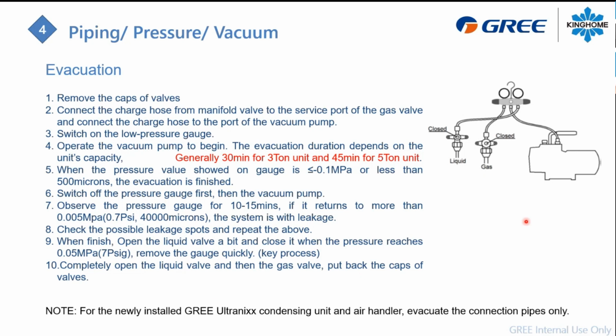So you will attach your vacuum pump, and then you will need to make two different vacuums, one for the liquid line and the other one for the vapor line, because the coil is already holding some refrigerant, so it's not communicating from one line to the other.